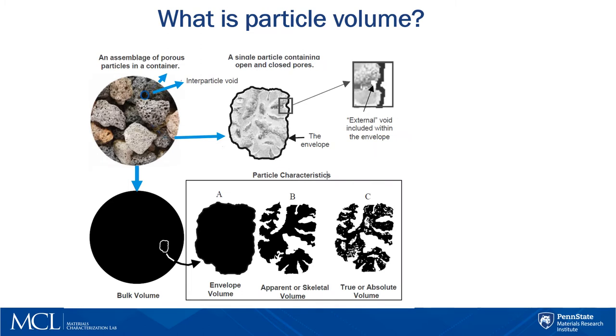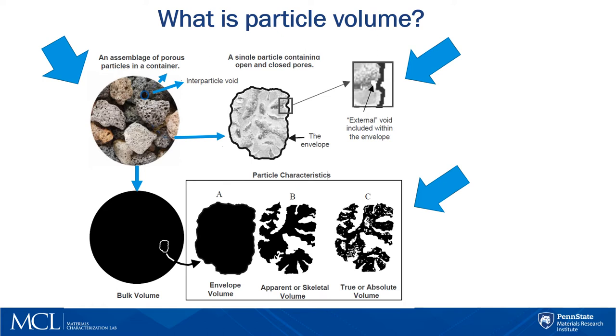Here you can see an illustration of various volume types. At the top left, there is a container of individual particles illustrating the characteristic of bulk volume, in which inter-particle and external voids are included. At the top right is a single porous particle from the bulk, with the particle cross-section shown surrounded by the envelope. In the illustrations at the bottom, black areas are analogous to volume. Illustration A is the volume within the envelope. Envelope volume B is the same volume minus the external volume and volume of open pores. And C is the volume within the envelope minus both open and closed pores.